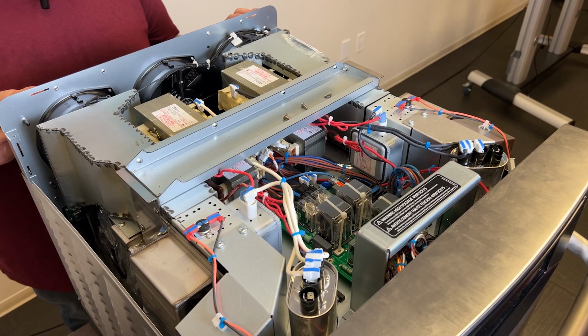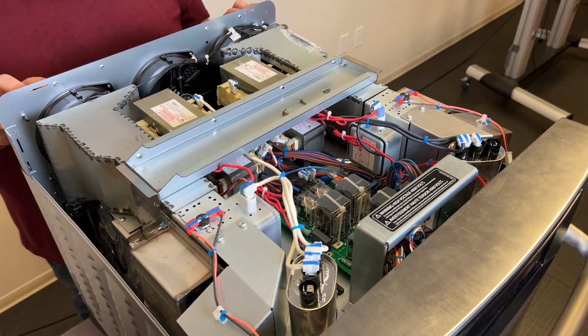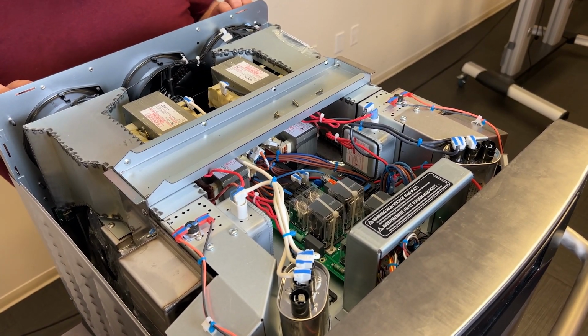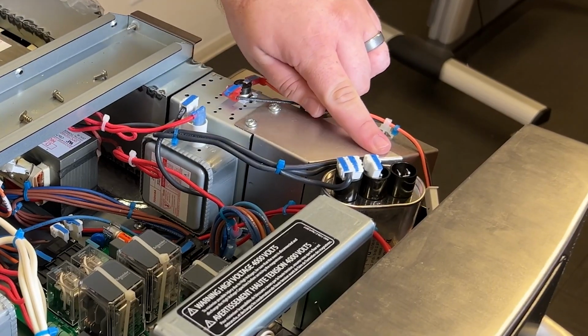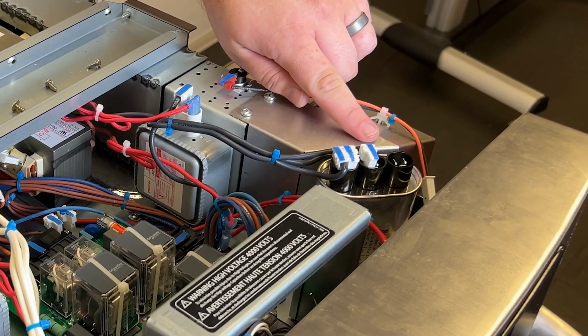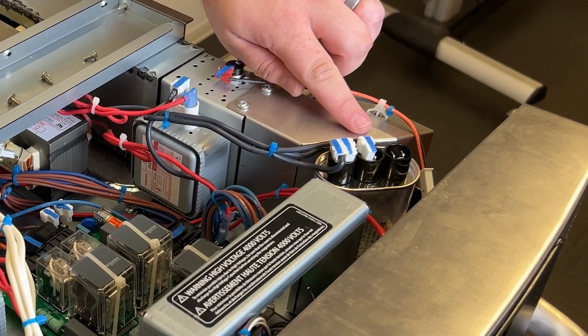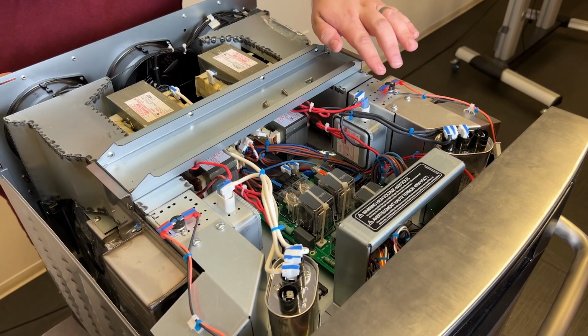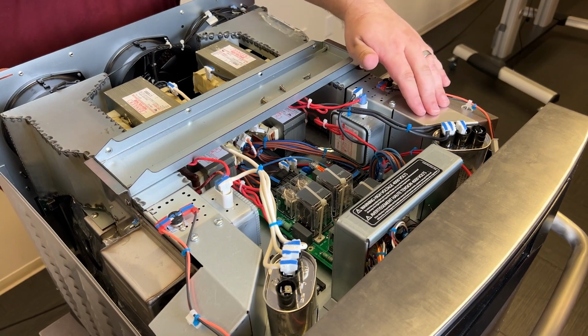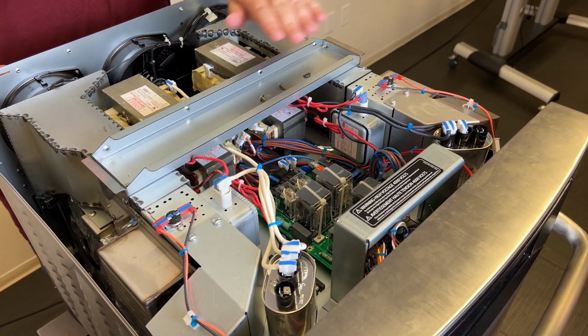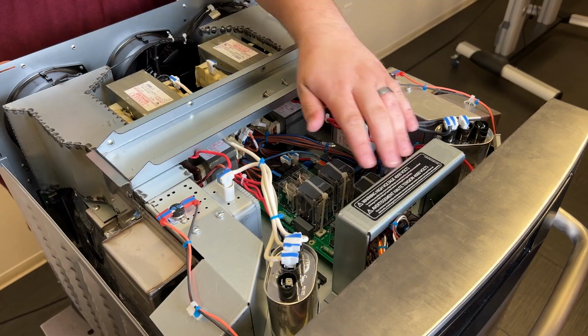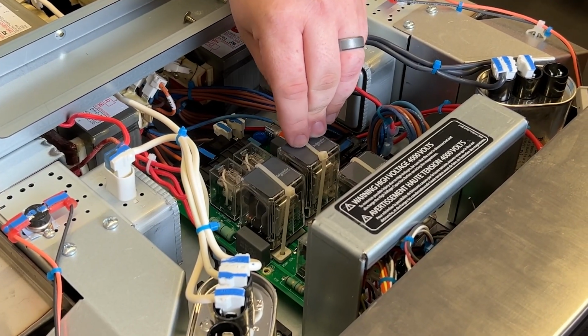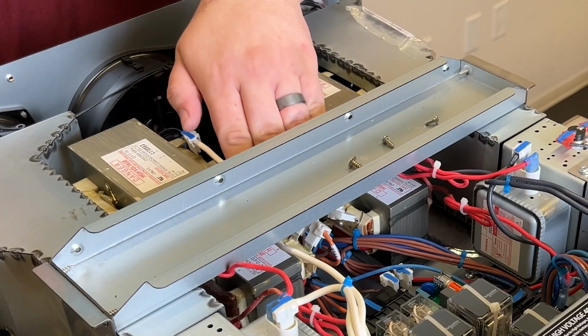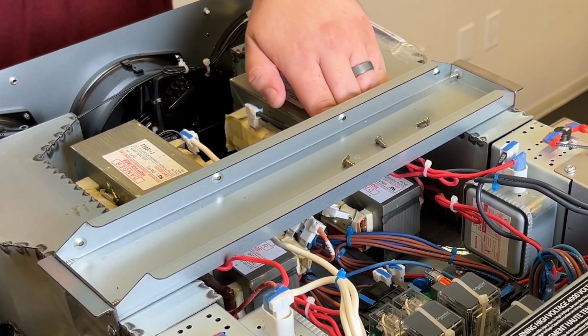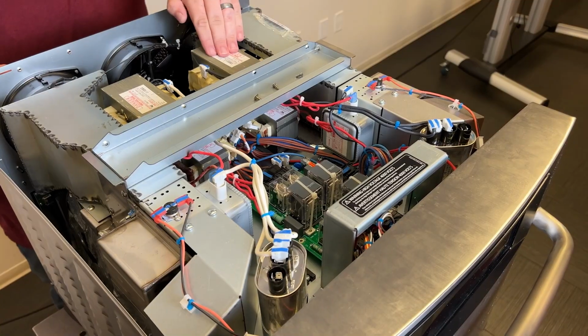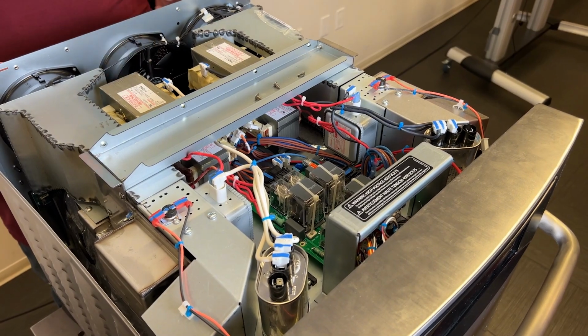Next, we have to remove all of our components from the electrical plate to access the top heating element. That includes both capacitors, which you'll want to confirm are discharged before removing. You'll also need to remove the magnetron along with both of its cooling ducts, both cross members, the relay or triac board, the filament transformers underneath the cross member, and the high voltage transformers in order to get to the electrical plate.